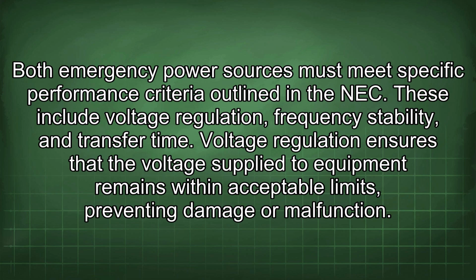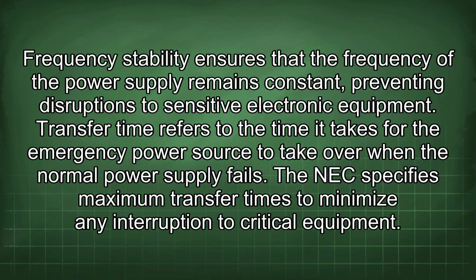These include voltage regulation, frequency stability, and transfer time. Voltage regulation ensures that the voltage supplied to equipment remains within acceptable limits, preventing damage or malfunction. Frequency stability ensures that the frequency of the power supply remains constant, preventing disruptions to sensitive electronic equipment. Transfer time refers to the time it takes for the emergency power source to take over when a normal power supply fails. The NEC specifies maximum transfer times to minimize any interruption to critical equipment.